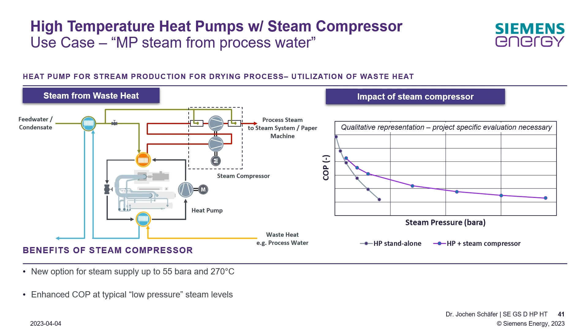Let me summarize my point. First, electrification of the heating sector is key to meeting global emission reduction targets. Heat pumps allow for energy efficient decarbonization of the heating sector. High temperature heat pumps facilitate low carbon heat supply to district heating systems and process industries, and subsequent steam compression opens up new possibilities for steam supply up to 55 bars and 270 degrees C.